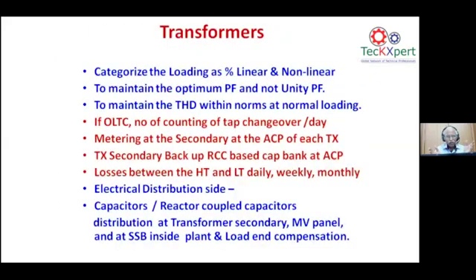To start with, on the transformers, let us say we have the transformers in the industries. I'm talking about the HT consumer only. Let us see, it has a mixture of linear and non-linear loads. At the moment, everyone has already burnt their fingers by keeping a unity power factor, maybe it's a KVAH billing or a KWH billing. What is the stable power factor to be kept for the given industry for a mixture of loads? It varies from industry to industry, but you have to choose the optimum power factor and not the unity power factor at all.